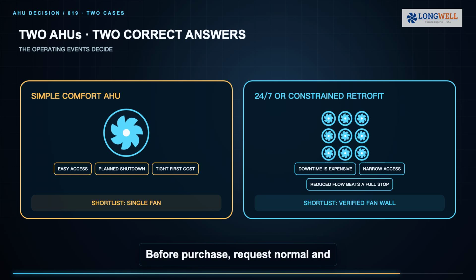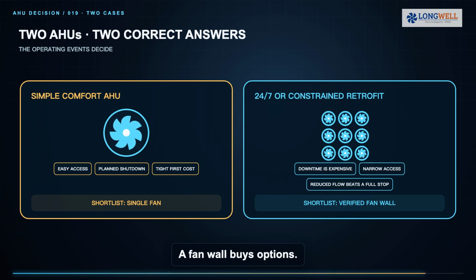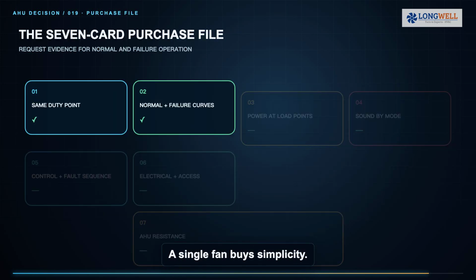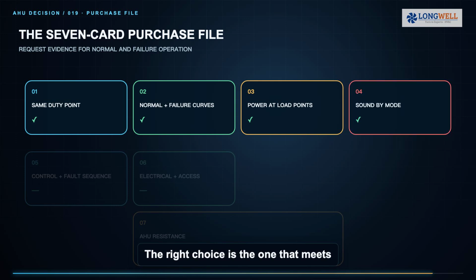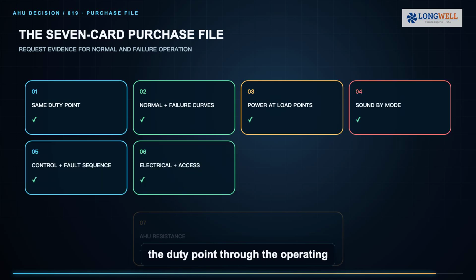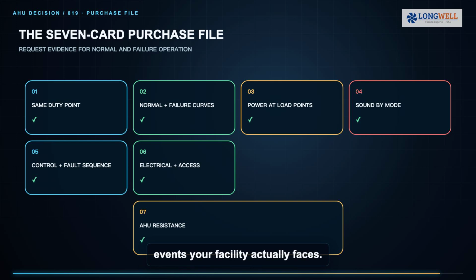Before purchase, request normal and one module off curves, absorbed power across the annual load points, sound data, control and failure sequences, electrical distribution, service clearances, and the actual AHU resistance calculation. A fan wall buys options. A single fan buys simplicity. The right choice is the one that meets the duty point through the operating events your facility actually faces.